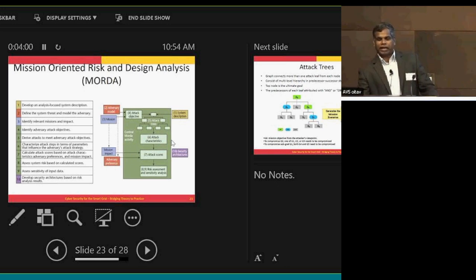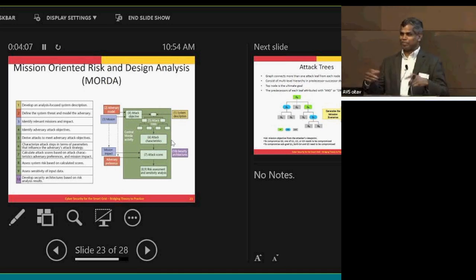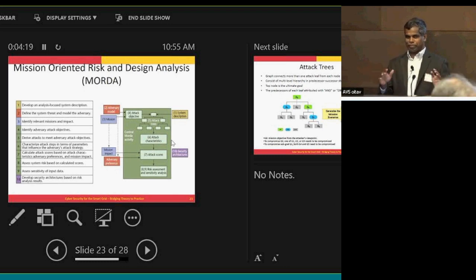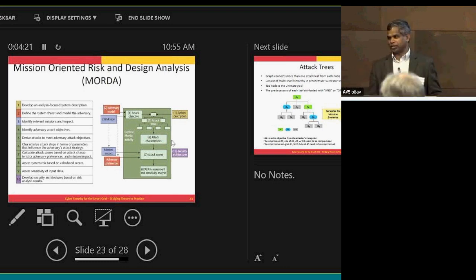Okay. And another important thing is, even doing patch management, with your Windows operating system, a patch update happens and it reboots. You can't do that. So the cybersecurity lab or the test bed does the patch update first, makes sure everything is working for some period of time, observes, then they go into the production system. That's how it is done, yeah.